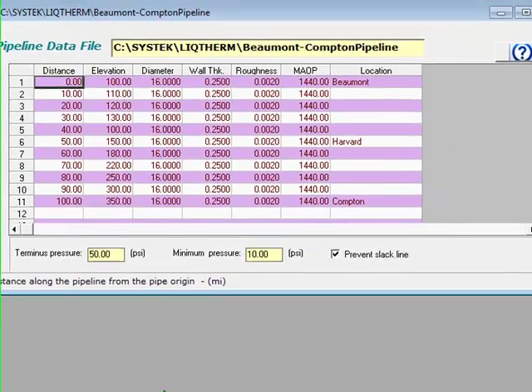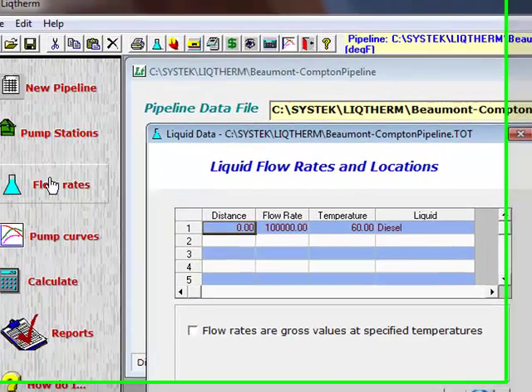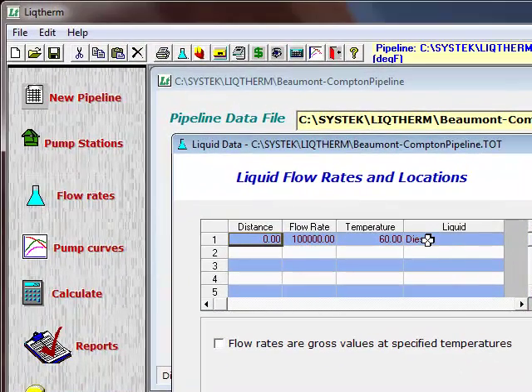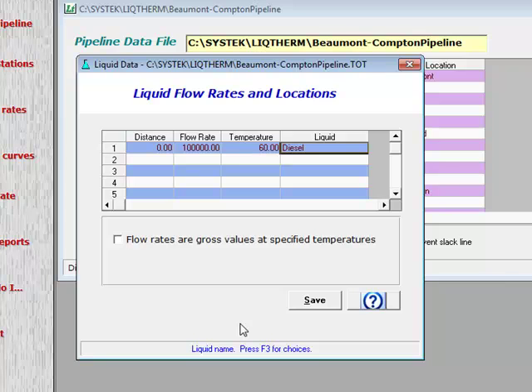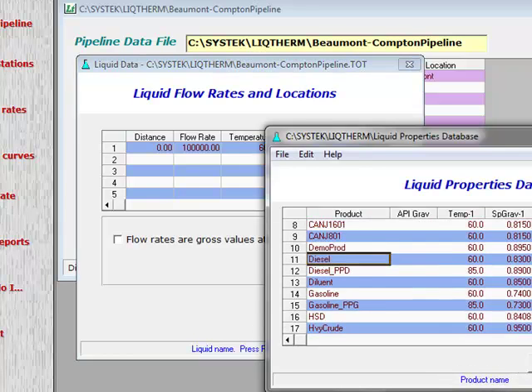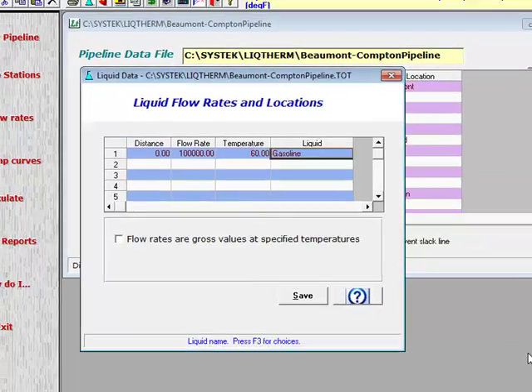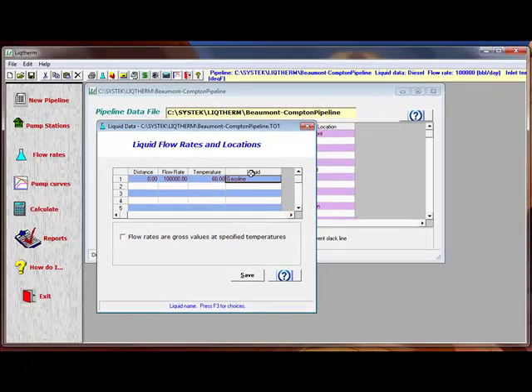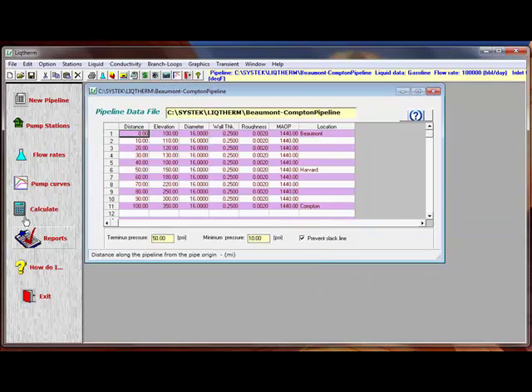The next step is to determine the maximum flow rate possible considering these pumps but using gasoline as a pump fluid. So you go over to the liquid screen, push F3, change the product to gasoline, click save, and start calculations.